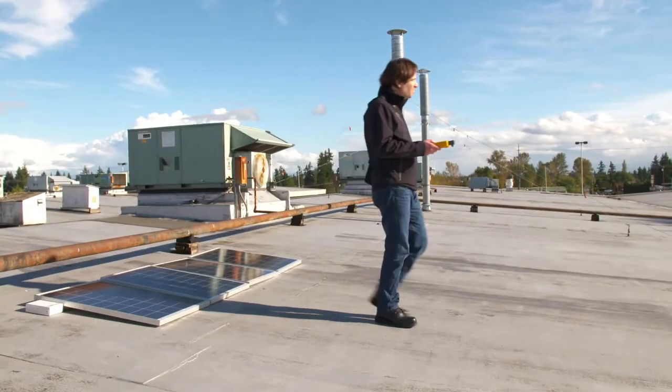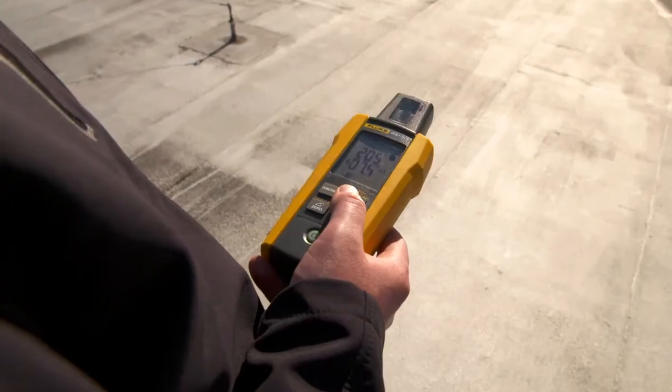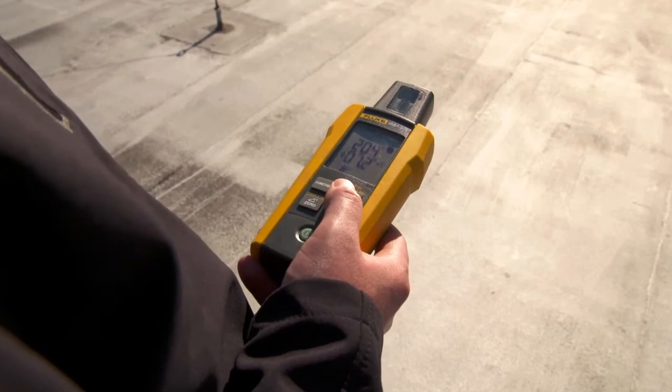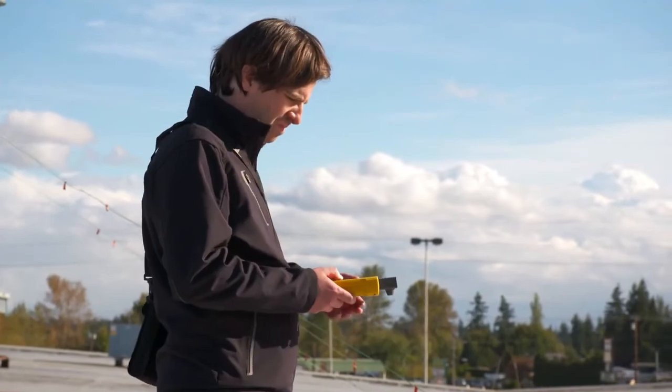This is why another step is necessary to verify the direction. Position the meter away from the panel and any other metal objects, with the tip of the meter facing in the same direction as the panel. Confirm your compass reading.